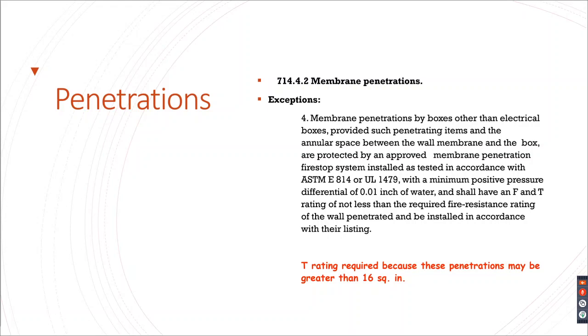In these cases, the T rating is required because these penetrations may be greater than 16 square inches. It doesn't have the limitations like the exception 1 did.